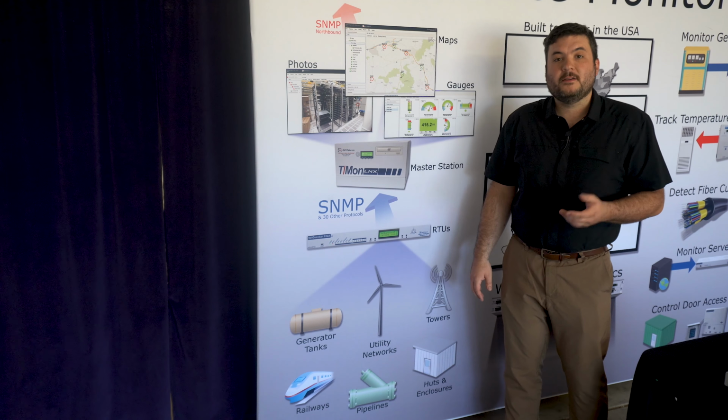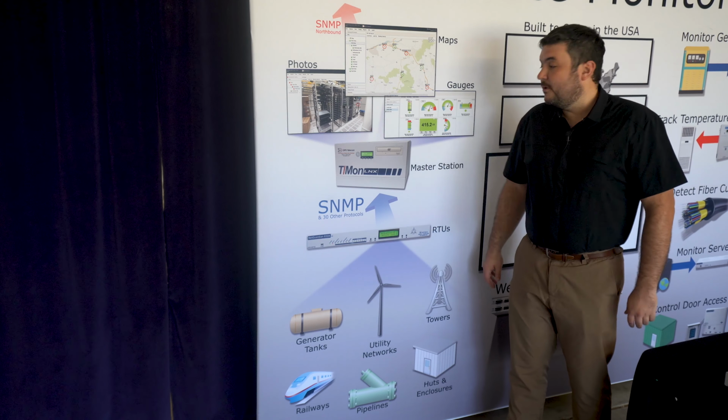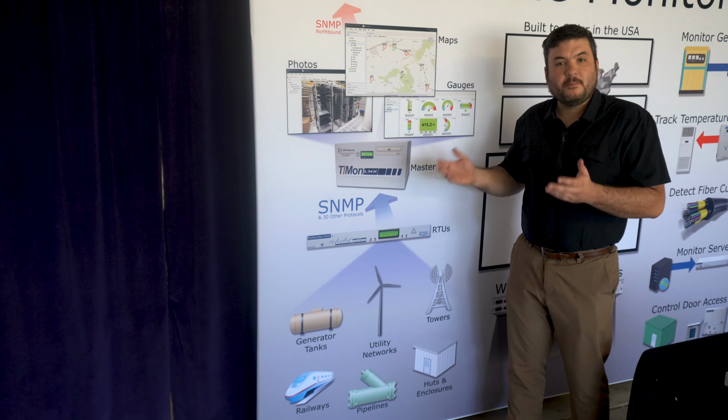If you have 10 sites or less, that could be your entire monitoring system. You just log into the web interface, maybe set up email and text message alerts, and you can be done, and that can be a great system. But if you have more than 10 or 12 sites, really, an alarm master station of some kind is required.